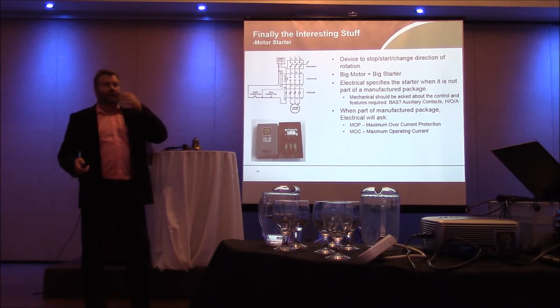So it tells me what size I have to make the protection and how many amps this thing is actually going to draw. And we're concerned about what size we make the protection because typically that pre-manufactured piece of equipment only has conductors of a certain size in it. And if I make the protection too large, I'm not adequately protecting the conductors inside the unit. And then the electrical inspector opens the door and he looks in and he says, wait a minute, that looks like a number 2 wire. No, change the breaker. And again, change the breaker means change order.